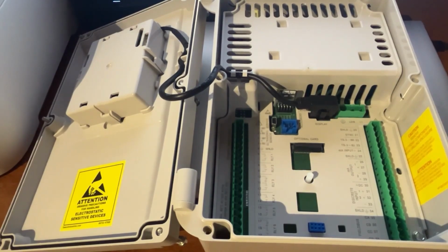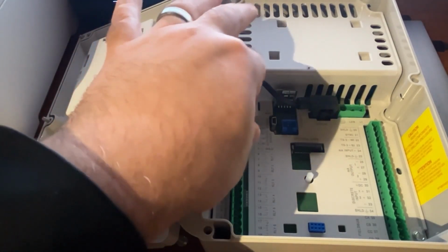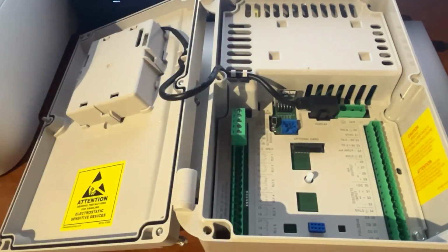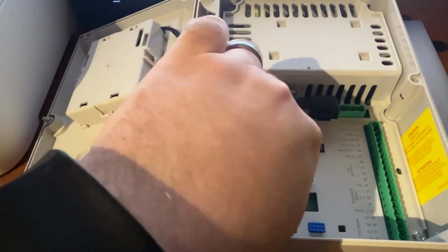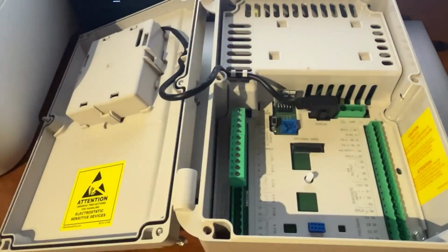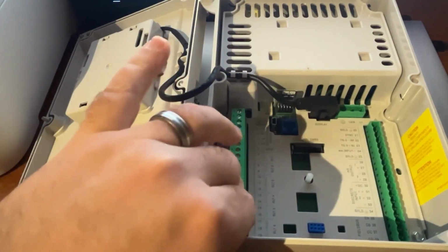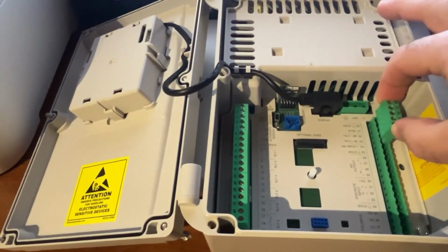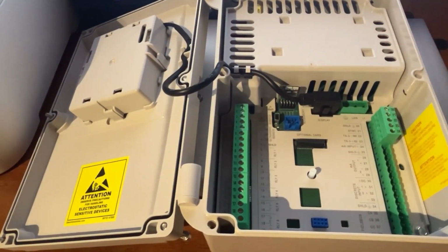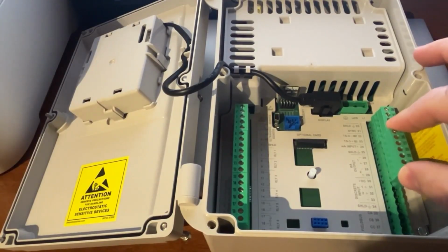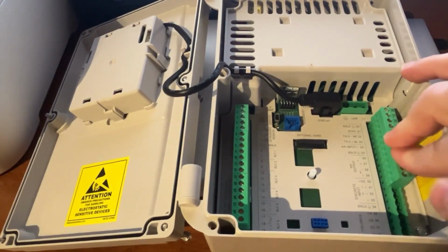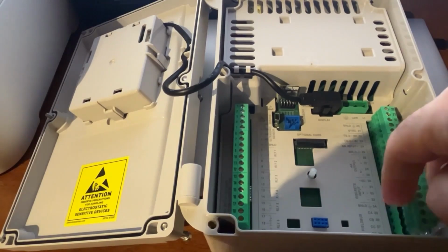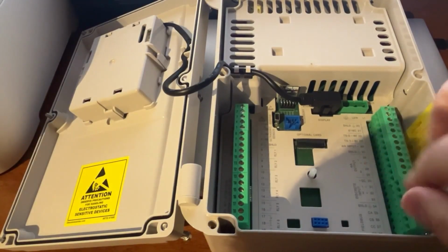I'm going to go ahead and take all of the removable terminal blocks and plug them into the device, and you will notice that they are marked with a number on them, which corresponds to the same number that is on the device inside. So it's very easy to identify where the terminal blocks go. And these, again, are removable so that when it comes to wiring, of course, you would normally wire these first and then plug them in. But just to give you an idea of how this works and some of the features here.